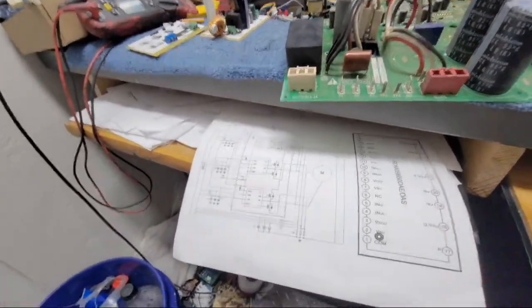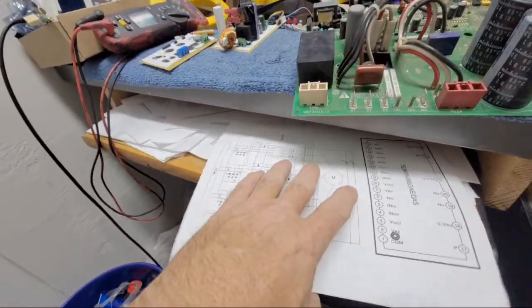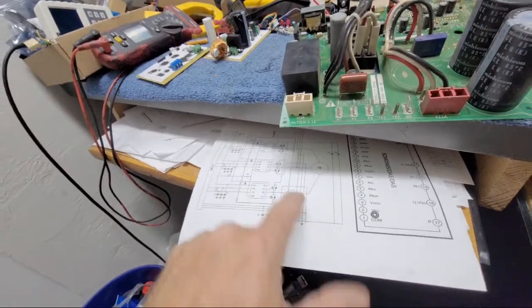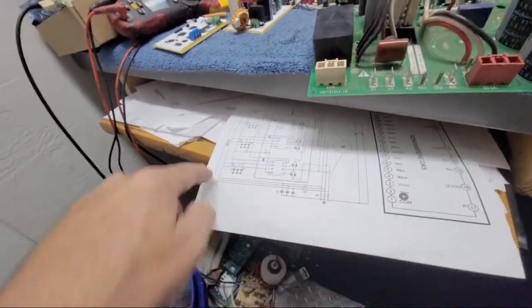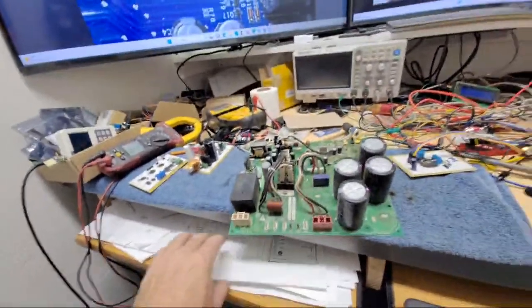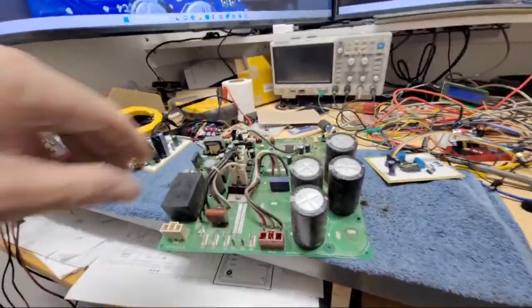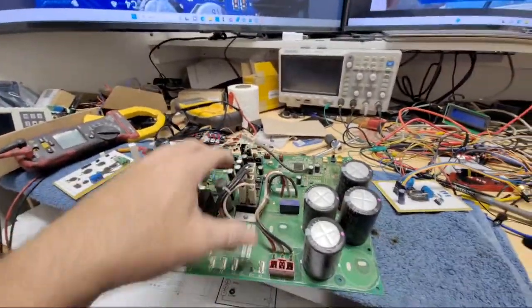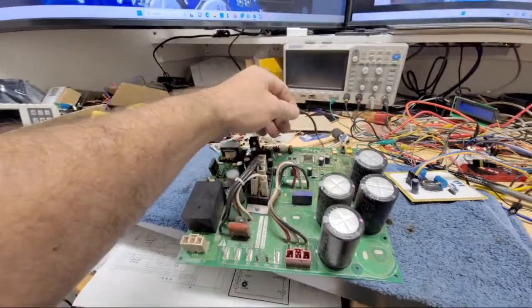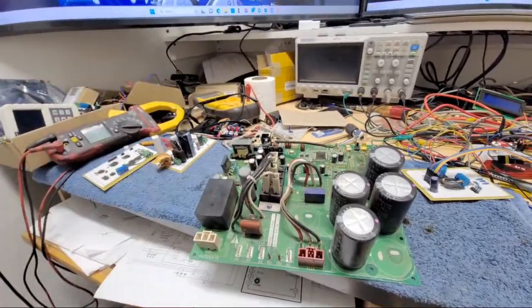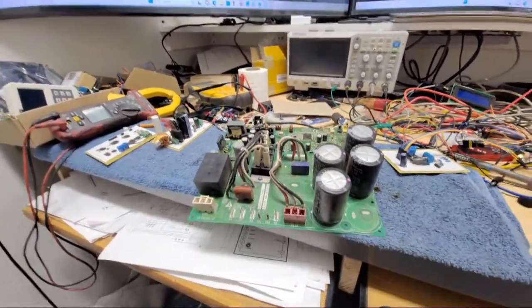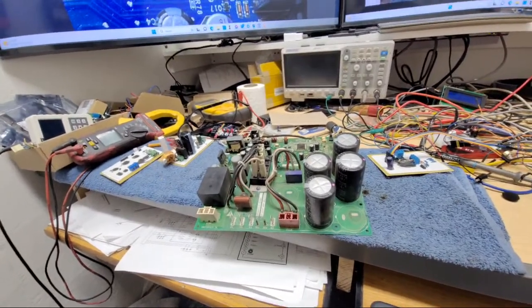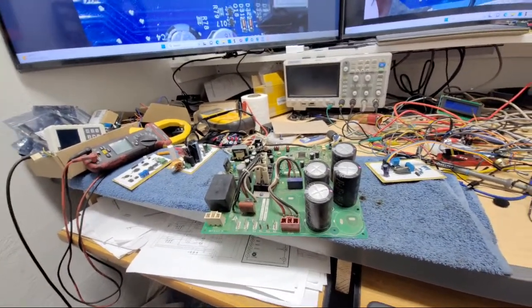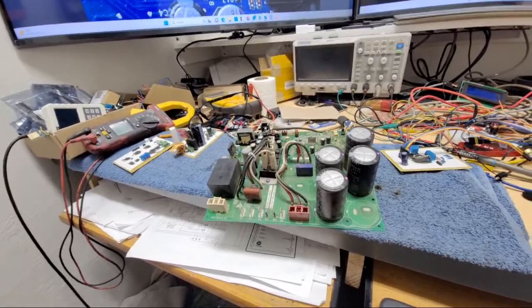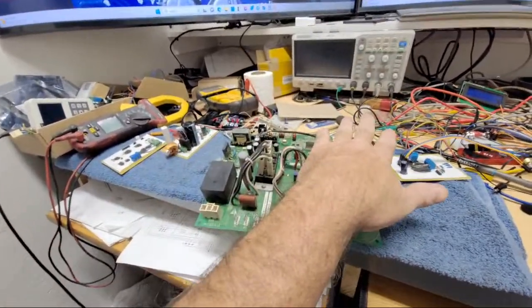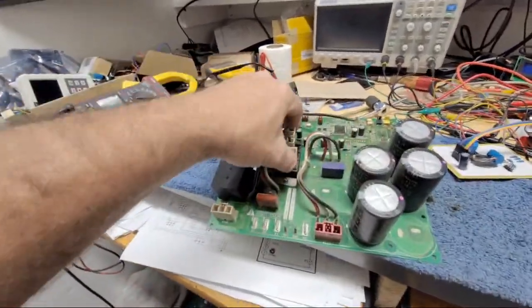But as I've learned, with brushless DC motors like ECMs, it's got feedback, which is this down here, going to the microprocessor to know the relative position of the motor, so it pulses that permanent magnet motor at the right time, which is what a lot of inverter compressors are. But for regular 3-phase or even single phase, you're just going to vary the frequency, so you still have to have the bank of capacitors to charge up, which here's your rectifier.